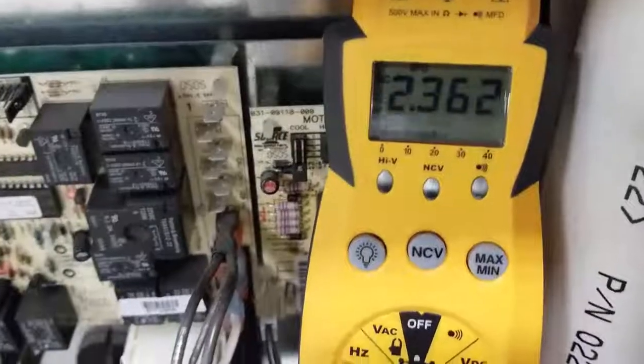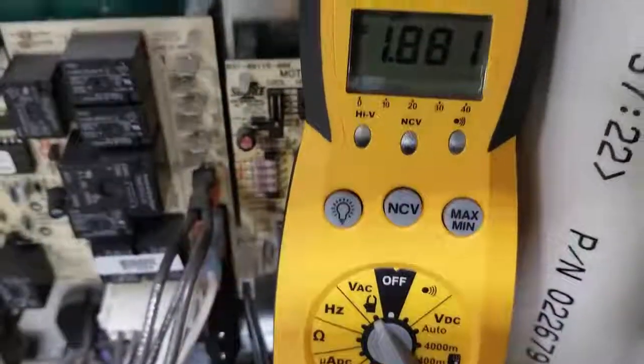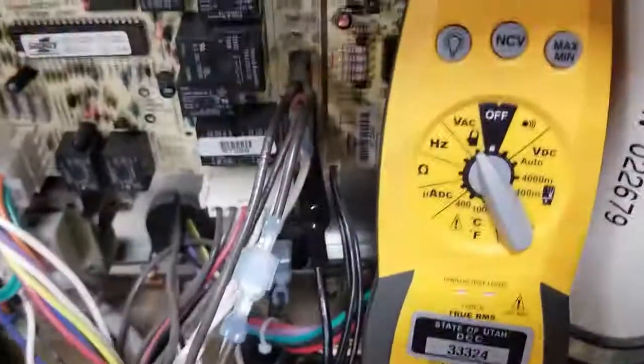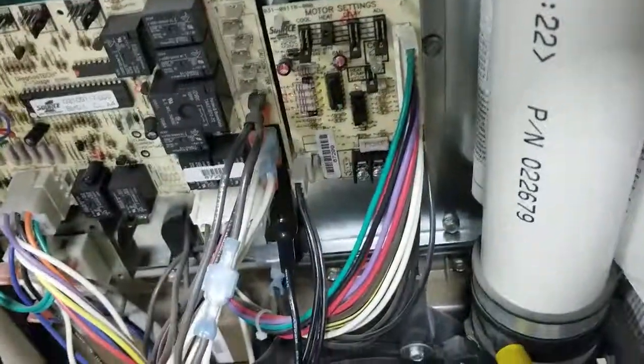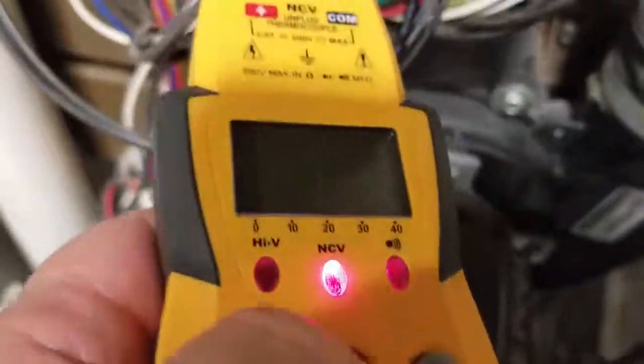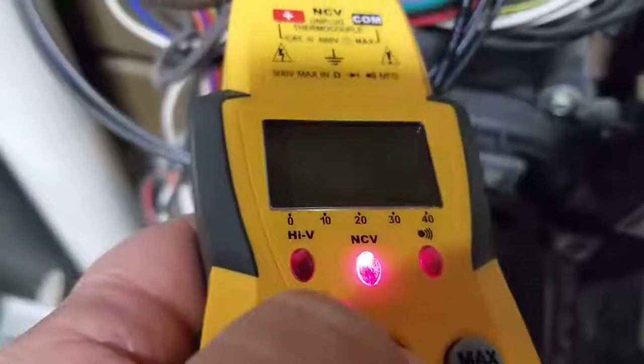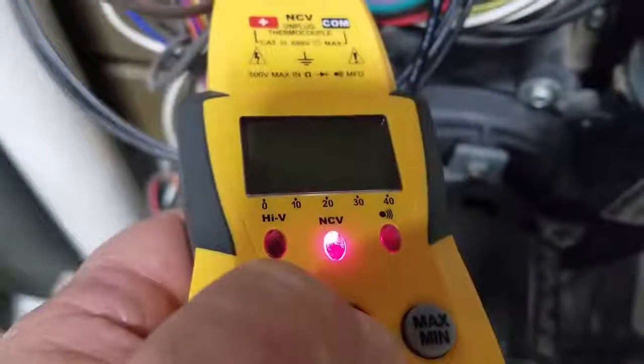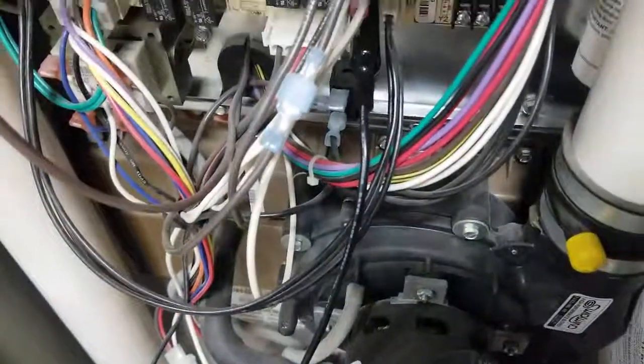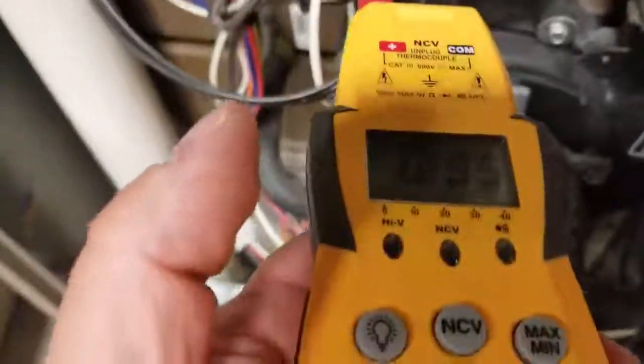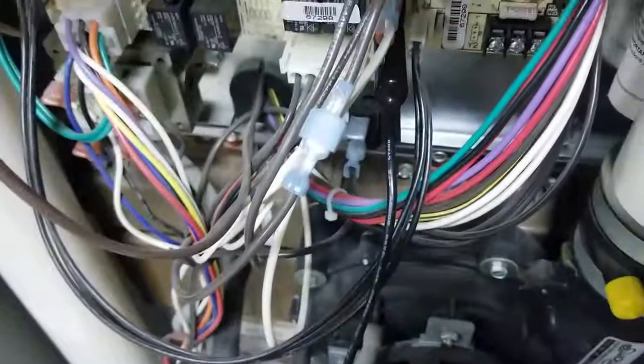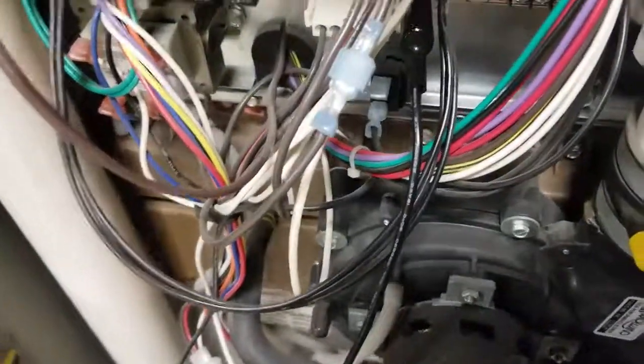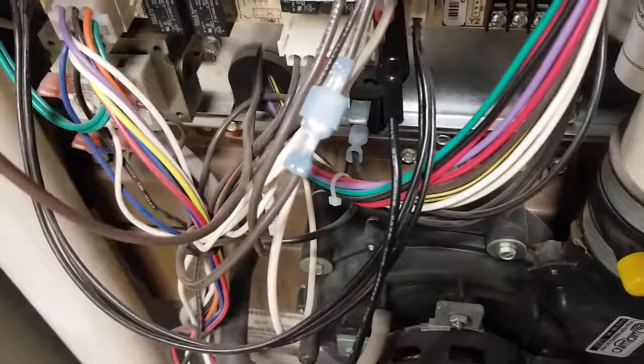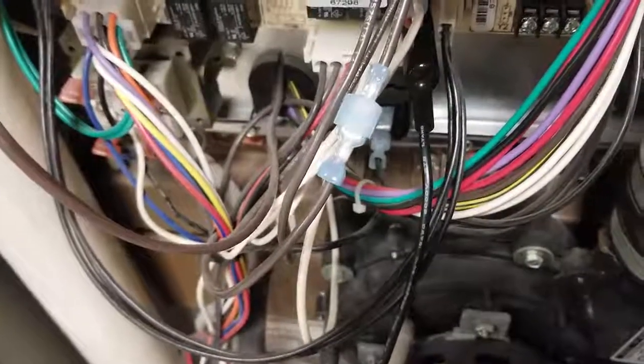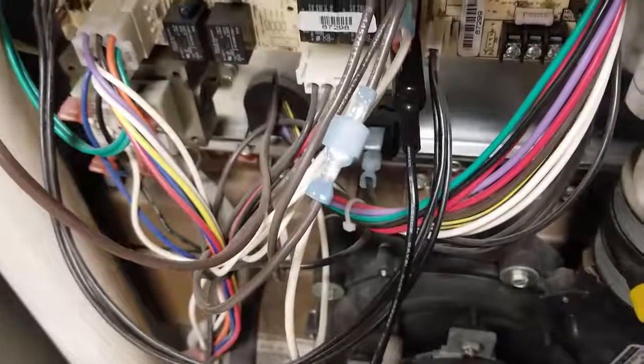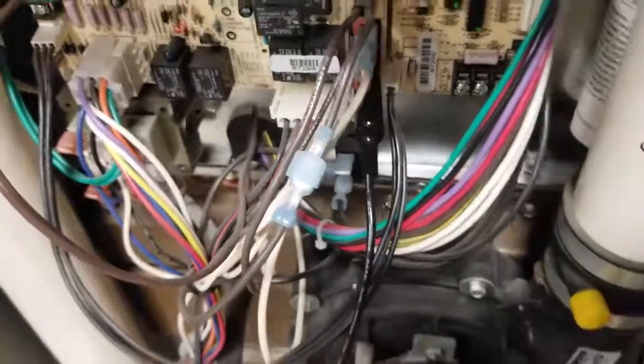This is the primary reason why using non-contact voltage testers is just really a bad idea. Again, you just saw there is no 120 volts, but the non-contact voltmeter tells me, oh yep, there's power to the furnace. So if I start troubleshooting based off of non-contact voltage, I'm not going to get anywhere. There is not power to this furnace, or at least there is not a complete circuit for this furnace to operate. There is power to it, but not a complete circuit.